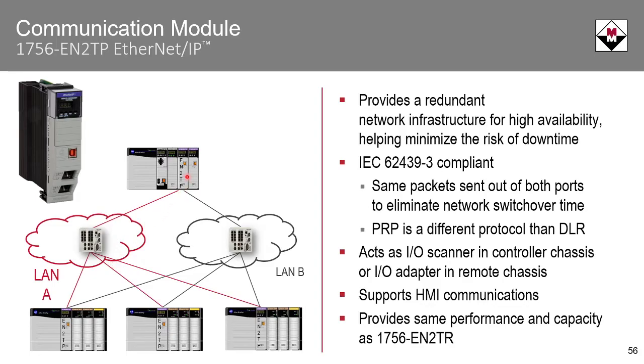So how this works is the source DAN sends the same frame over both LANs. The destination DAN consumes the frame the first time it is received and discards the duplicate when received. A DAN has one MAC address and one IP address. The frames that the DAN sends include the LAN ID. For more information on this type of network, feel free to contact me.